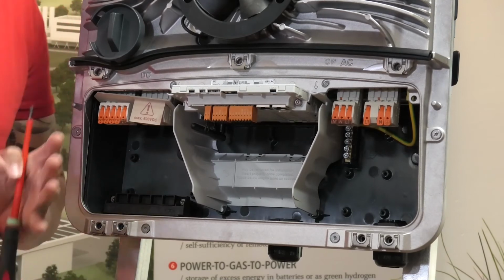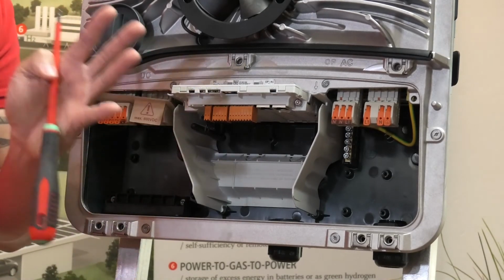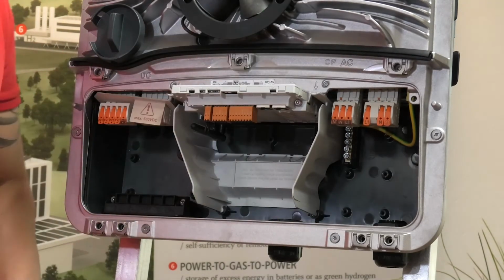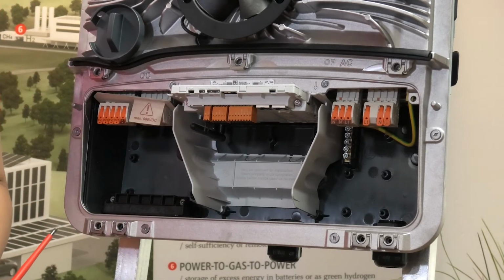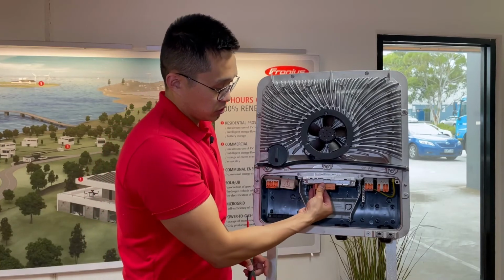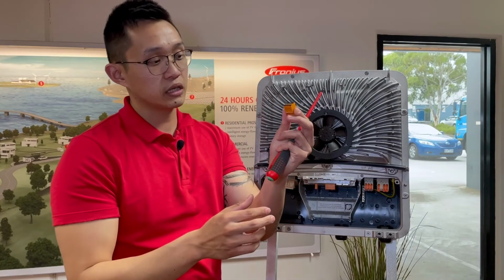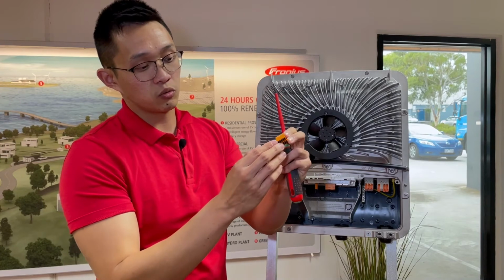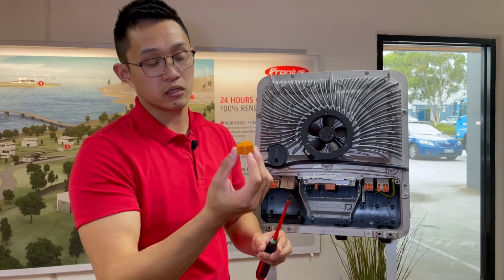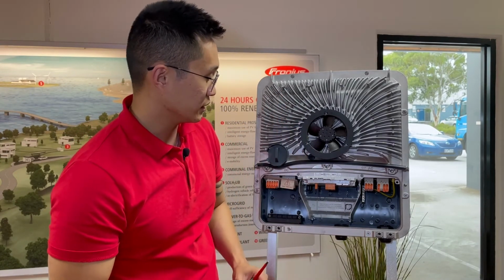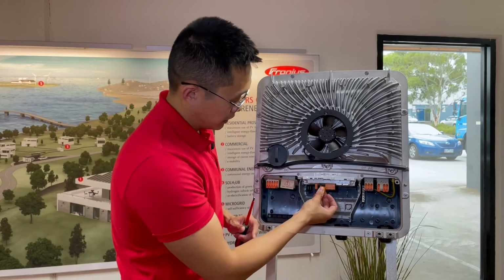From there, you'll see we have a new monitoring card, as if we combined the display and the data manager card. This new card is called the Pilot, and it has twice the amount of Modbus communication. For Modbus RTU, it's on this particular plug, where you'll see M0 and M1, meaning Modbus 0 and Modbus 1. I'll talk more about that later.